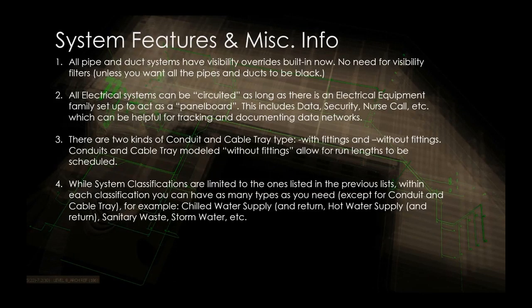What I found really useful is that if you use without fittings, you can pull up the length of the entire run. So if you're trying to determine your longest run in a building, say from a patch panel to the furthest room with the furthest outlet, you can model a conduit all the way to the end using without fittings, then pull up the length of that conduit. It should be accurate provided you model the conduit where it's actually going to go. That can be pretty useful, as anybody who's tried to find the longest runs for a data network would probably know.